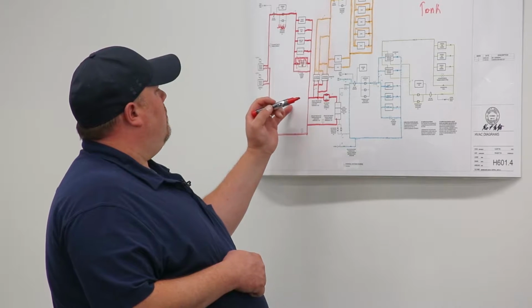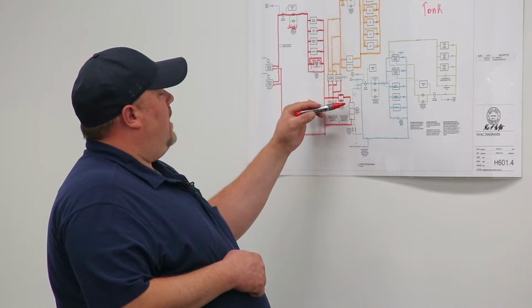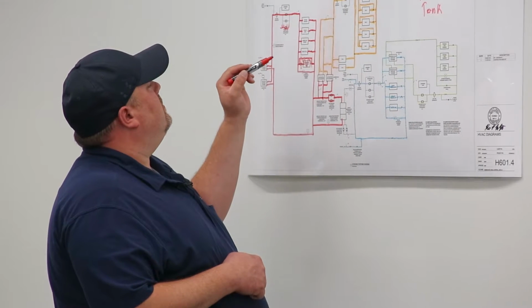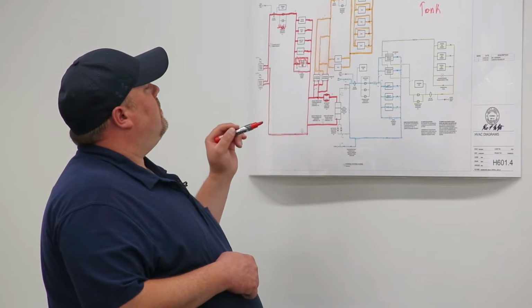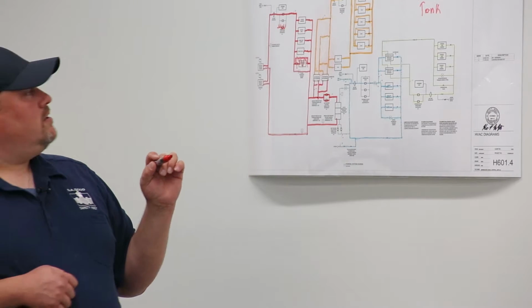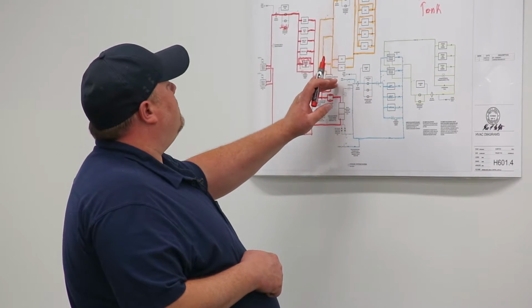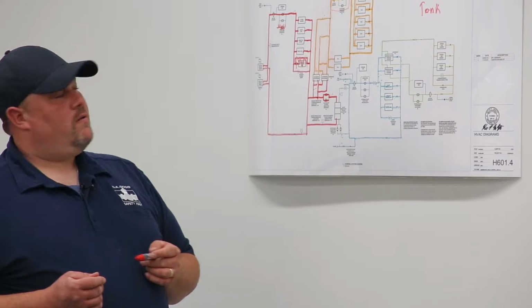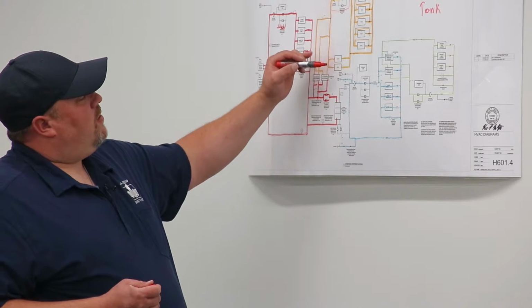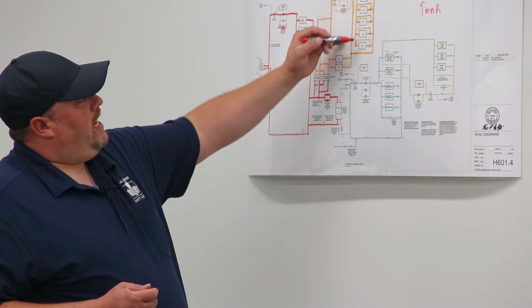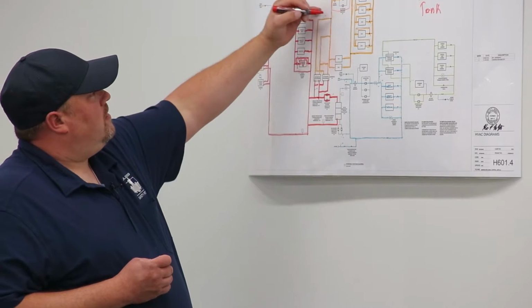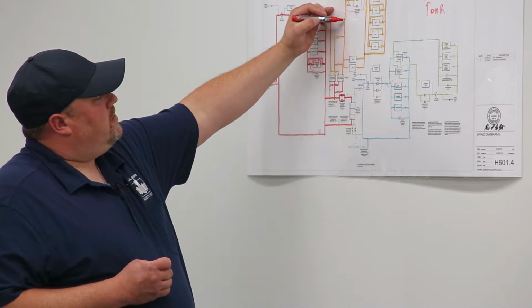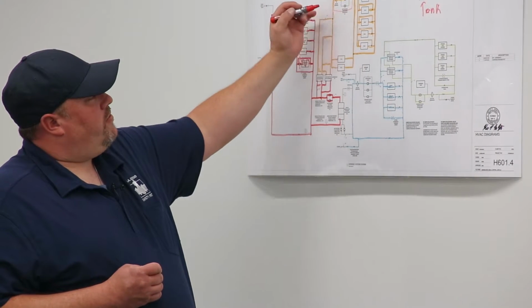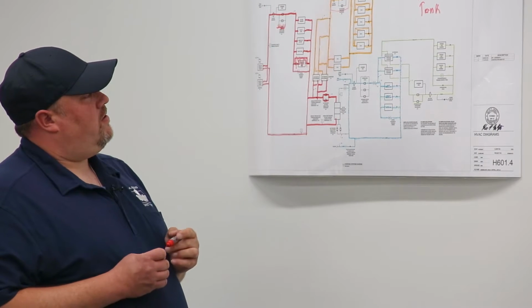In the winter months, as the extra heat is generated from the chilled water, it can be rejected through these heat rejection heat exchangers. And then that can be sent up into the loop and can be absorbed throughout the preheats of the air handler units and help preheat the air as it goes through the building. Or exhausted through these exhaust fan coil units if not needed to preheat these air handler coils. And it can go either way as it comes in through this three-way control valve. It can choose to go through the air handlers or be rejected through the exhaust fan coils. I think that just about covers our heating loop.